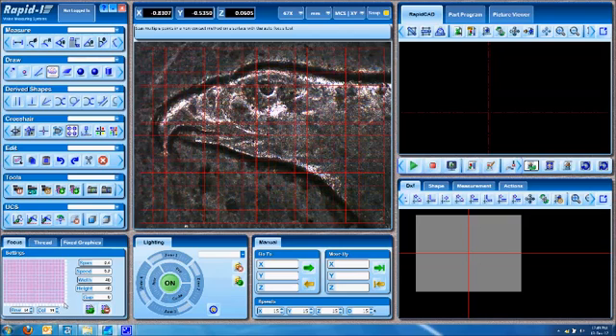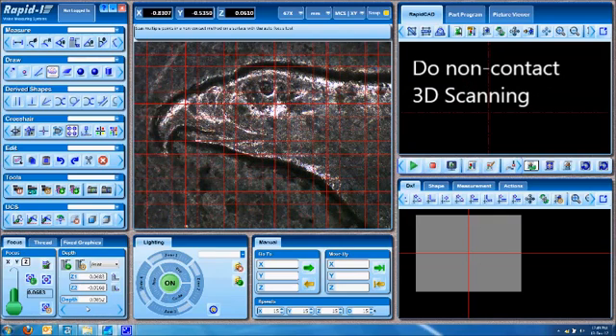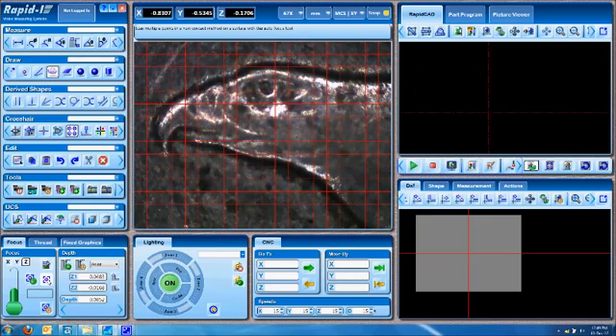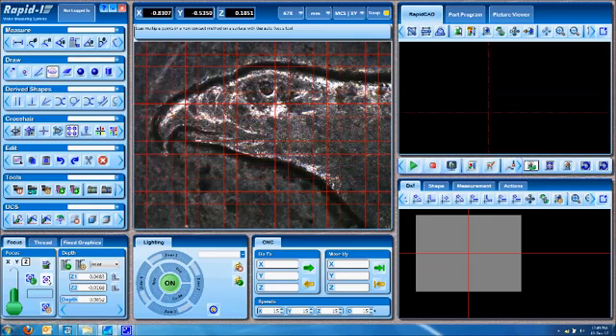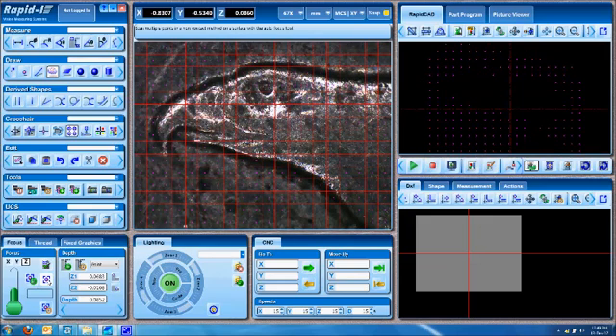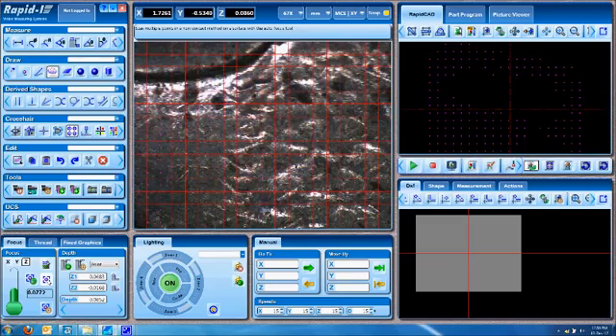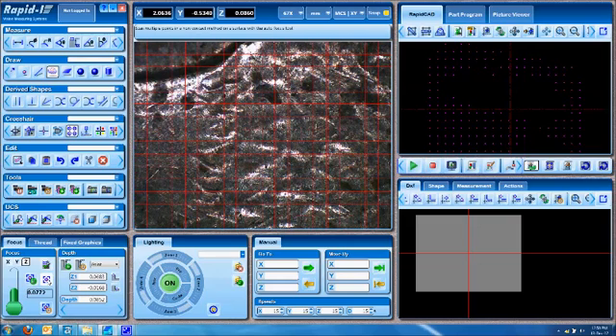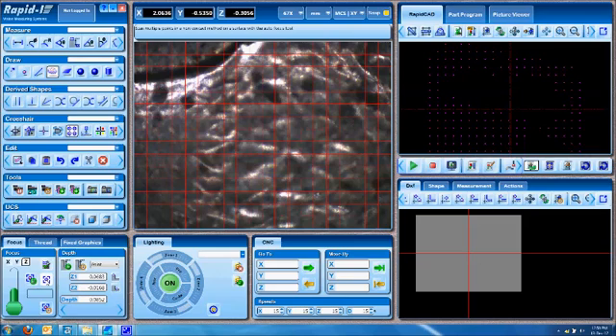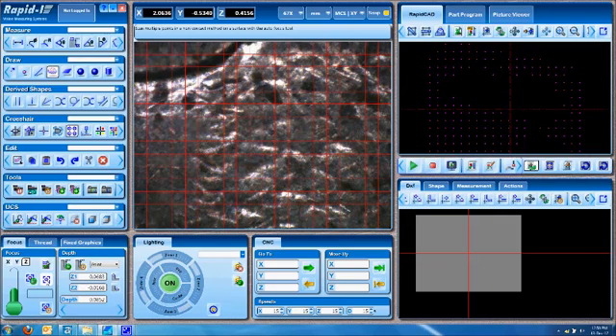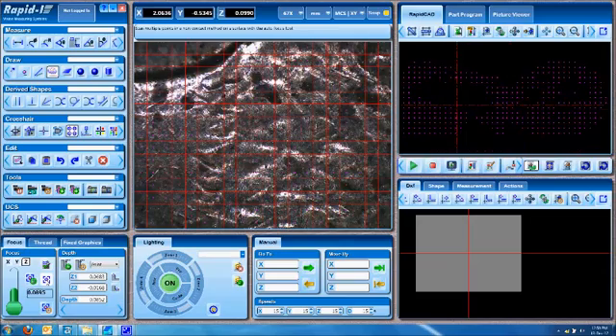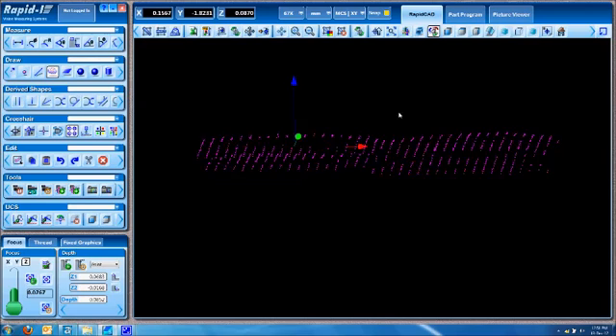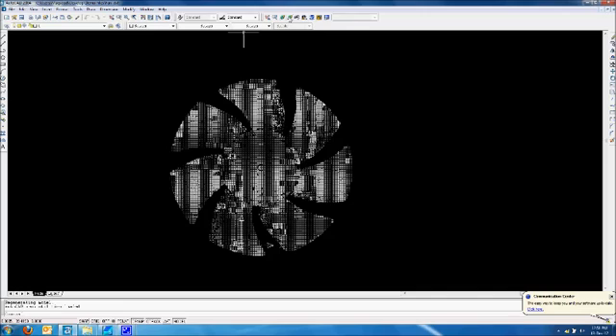We can now scale the number of boxes into a grid and do a complete non-contact 3D scanning of the component. Once one frame is done, it moves to the next one. You click on focus again, and it focuses and takes as many points as it can get. You can do the scan at any density you'd like, maybe even three microns every point, at any area you would like. You can switch on the 3D mode and see your cloud points.